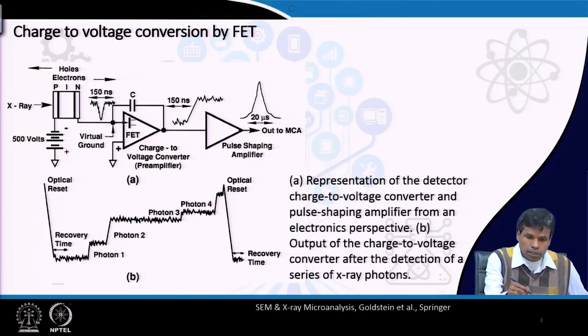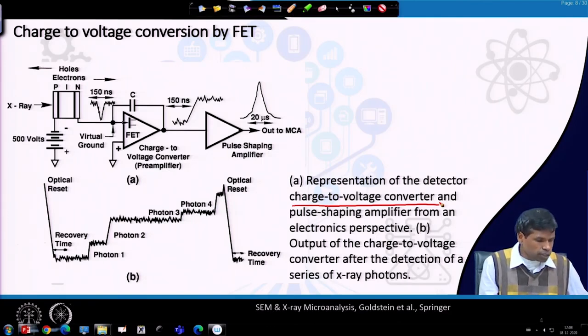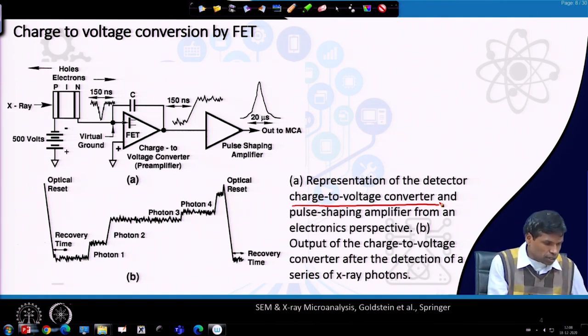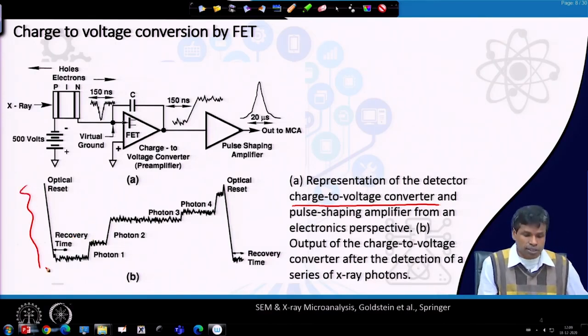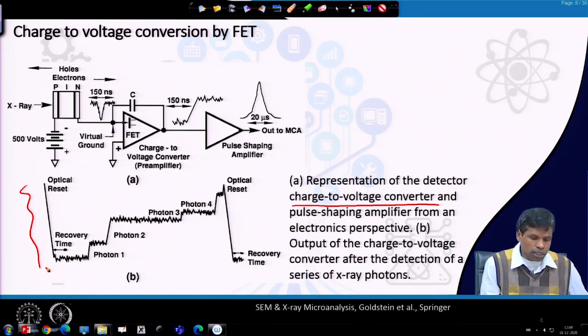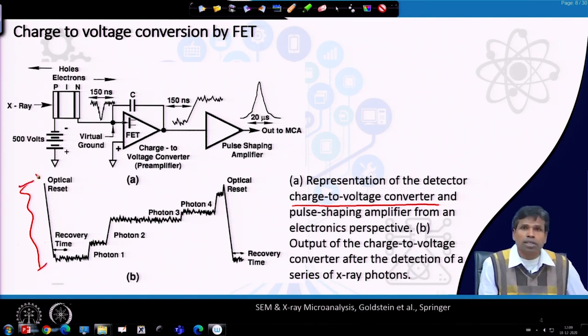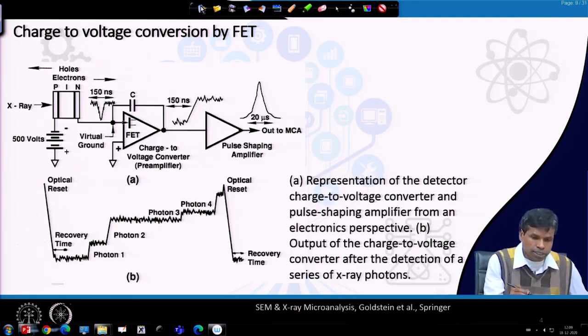This is a charge-to-voltage converter. The charge is deposited to a capacitor, and the voltage steps are proportional to the incident X-ray energy. By knowing the voltage steps, we are able to determine what energy the X-rays falling onto the detector have, allowing us to calculate the energy of the X-rays.